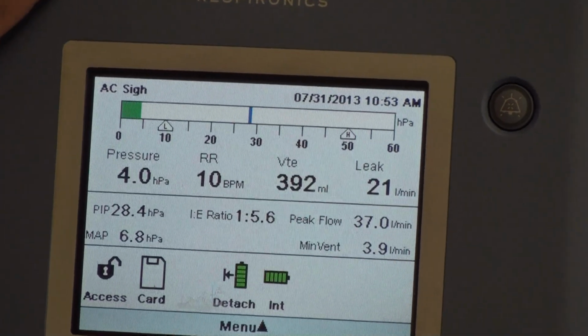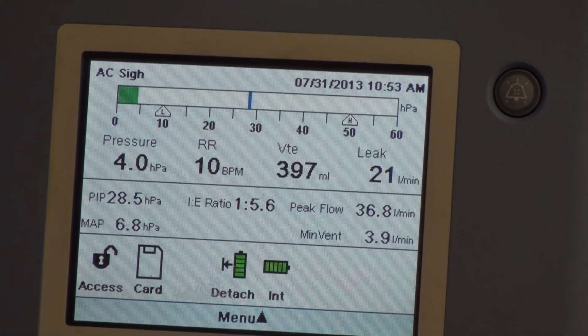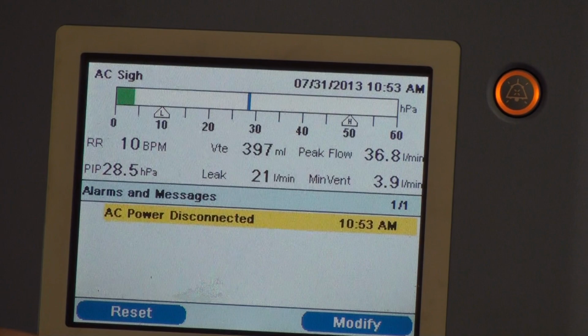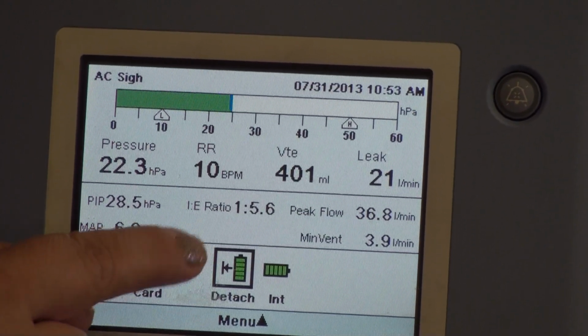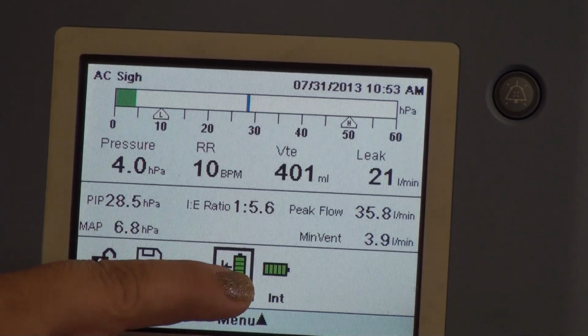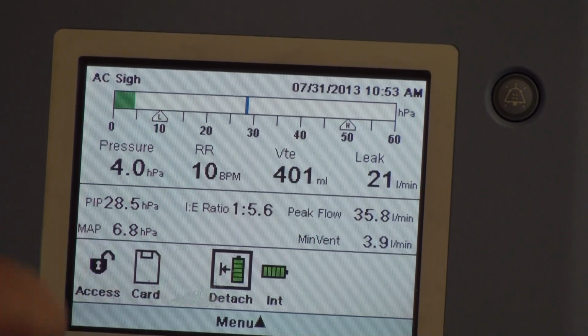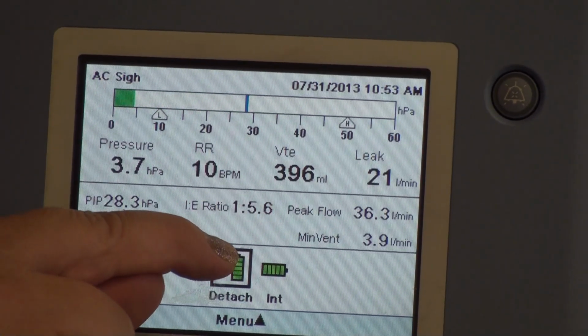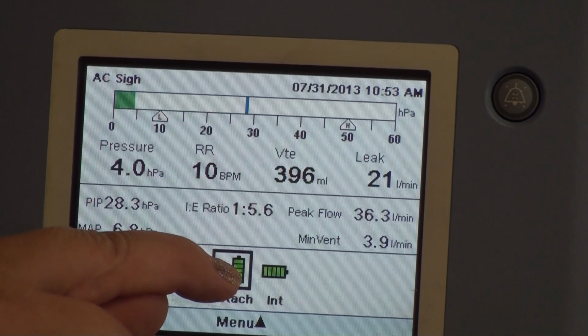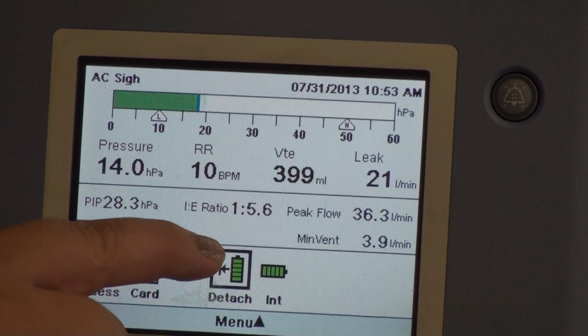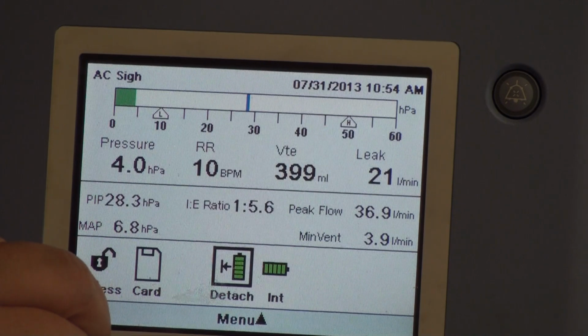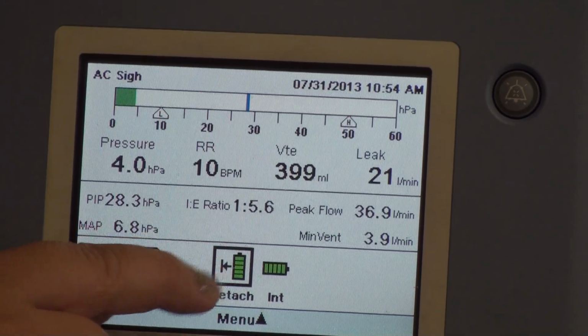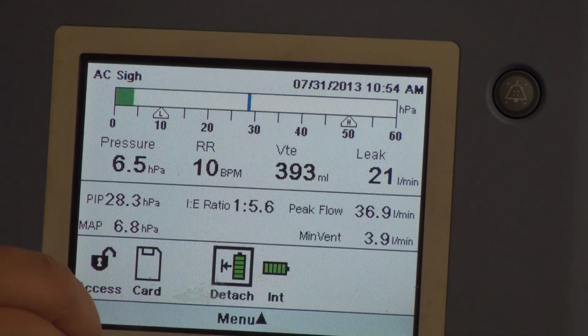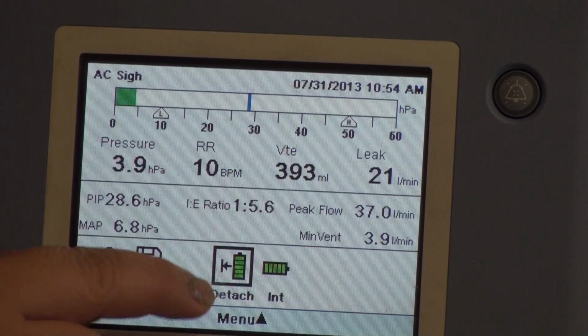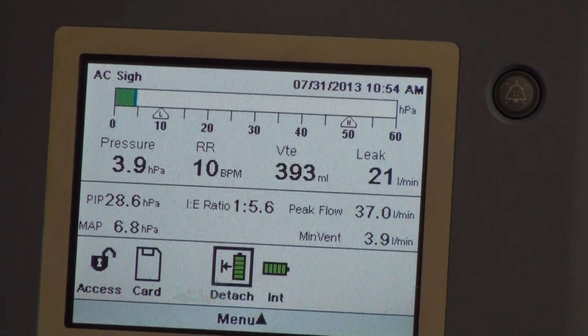For example, if I take the power out of here, first of all, it's going to let me know I did that. Second of all, you're going to notice a box now is around my detachable battery. That just means, okay, I'm running off of this battery right now. As I'm using it, all the little bars are going to go away until it gets down to the bottom bar. Then this little inside, when it gets down to 20 minutes' worth of battery life, will turn yellow. When it gets down to 10 minutes' worth of battery life, it'll turn red and say, yoo-hoo, you know what, I'm going to change to my next battery source, which is going to be my internal battery.